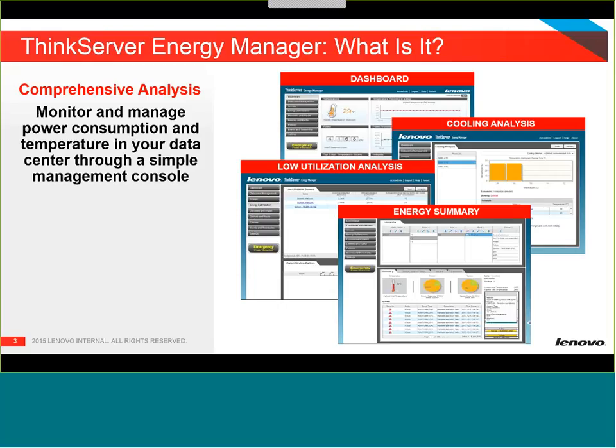You may know that as the IMM interface, or the Dell iDRAC interface, or the HP iLO interface, or the node manager interface. It'll access the server telemetry data through that interface, and then use that data en masse in a data center, or in a room, or in a row, or in a rack, assessing the power consumption and the thermal data to identify where we have lower, underutilized systems, where we have appropriate energy consumption, where we have appropriate thermals, and if not, it'll provide suggestions on what to do in respect to those things.